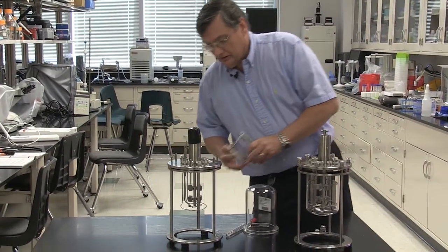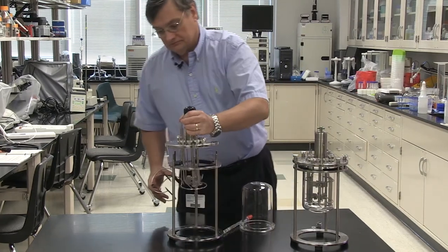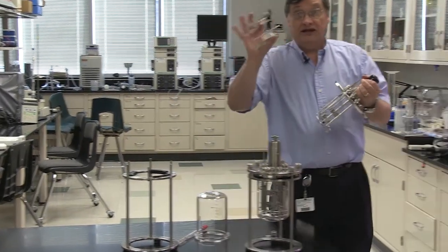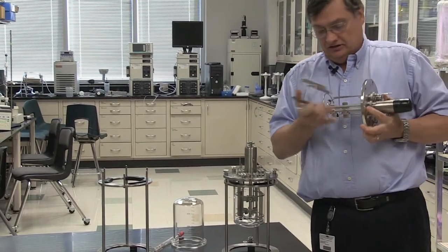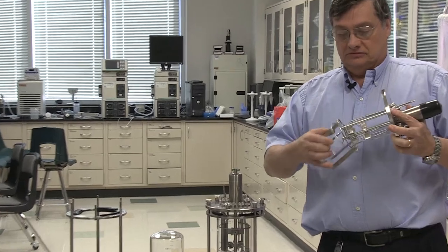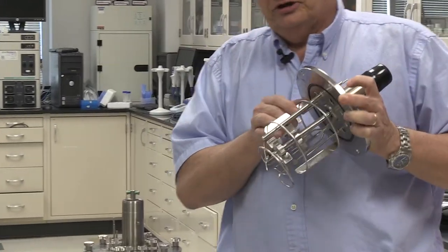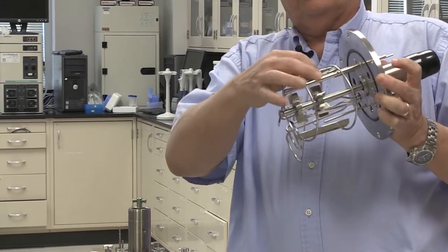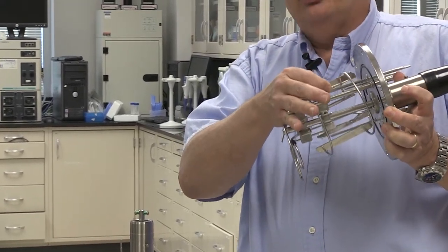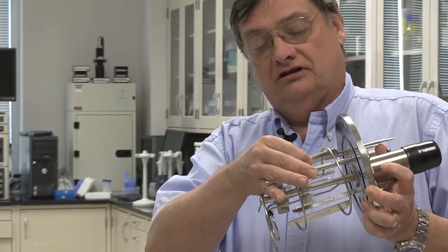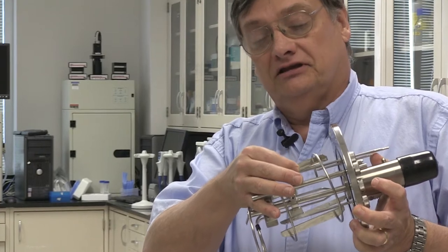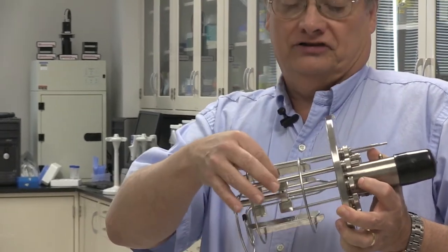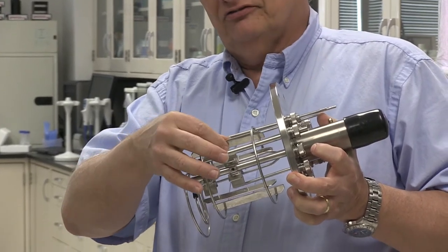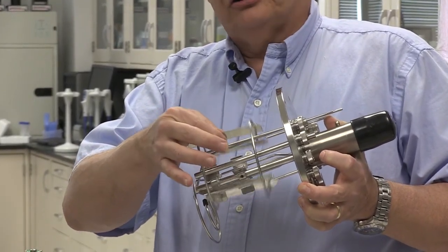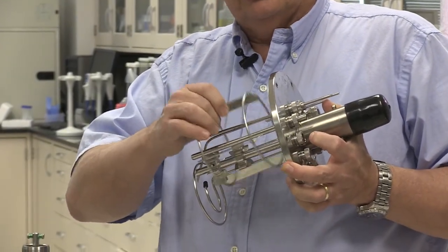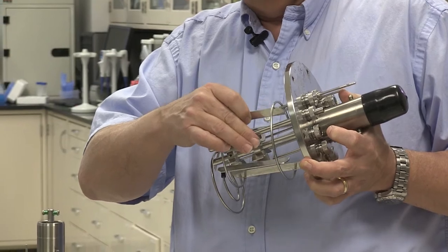Over here, don't want to forget this guy. This guy's called the baffle, right? And so, if I can get it on here, it's a trick. So it goes on here so that, like I say, these blades kind of oppose the circulation that the impeller is giving to the media to create turbulence. So, like I say, the faster the RPMs of the impeller, then the more oxygen that you're going to be putting in. And the control unit is going to control the RPMs of the motor.